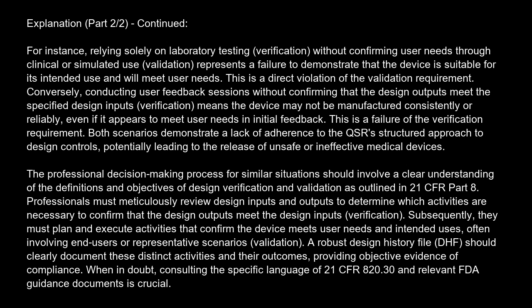The professional decision-making process for similar situations should involve a clear understanding of the definitions and objectives of design verification and validation, as outlined in 21 CFR Part 820. Professionals must meticulously review design inputs and outputs to determine which activities are necessary to confirm that the design outputs meet the design inputs (verification).